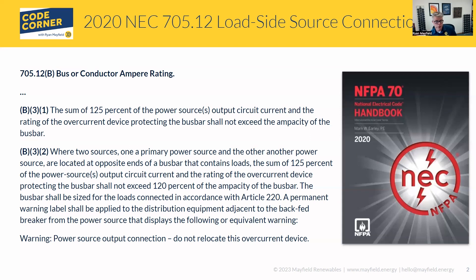So B31 is saying that we can take the sum of 125% of the power source output circuit current. 705 in general is not only for PV systems — it's for interconnected power systems and can cover a variety of different types. So the power source output circuit current is a generic term. More often than not, when we're talking about it, it's the output of our PV inverter, or the sum of the inverters.